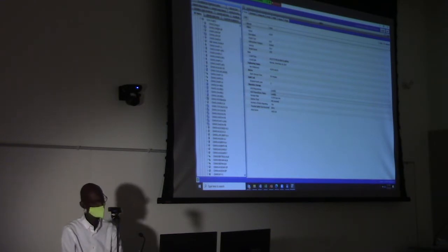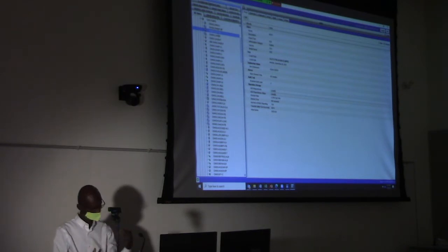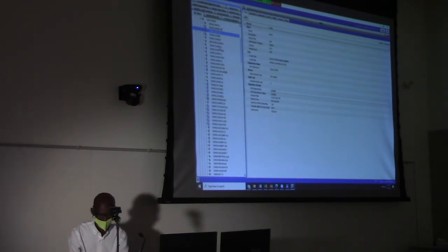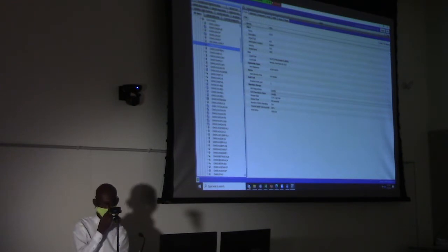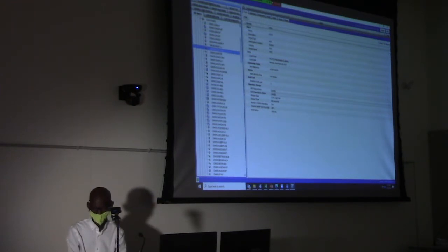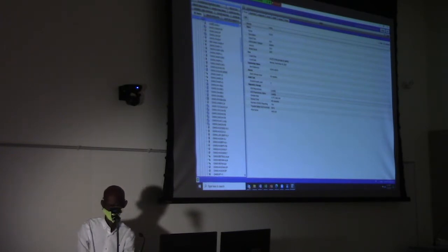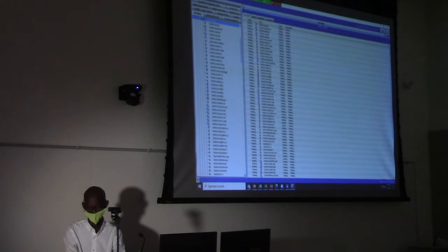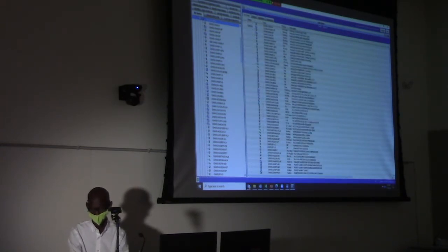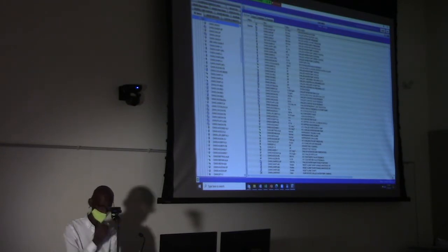So we have a chilled water temperature sensor here. We have a differential pressure. It tells us how much pressure we have for the chilled water coming in and going out. We have a pump command, for instance. We have a speed. So if I highlight this, you can see the ones we have here, and I'm going to show you what they mean exactly. And you can see the values. So it's a chilled water plant, real data here.